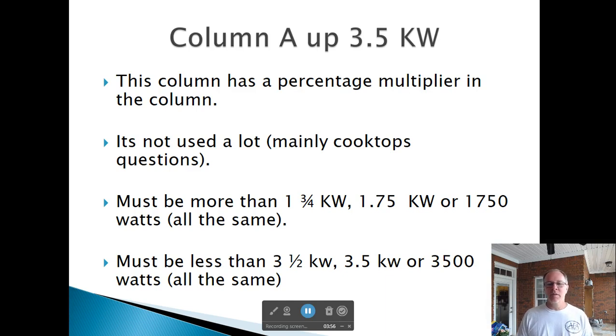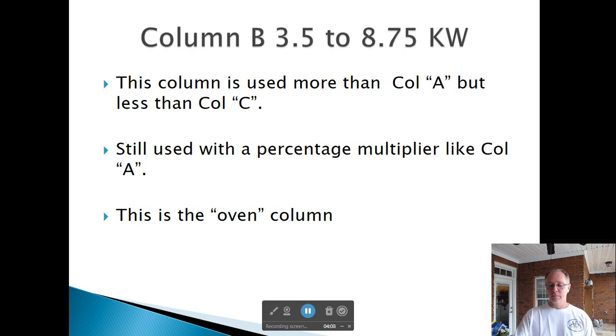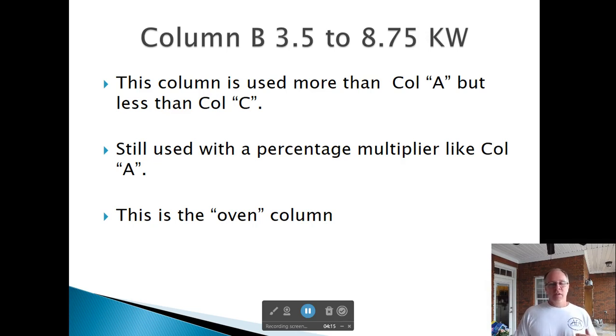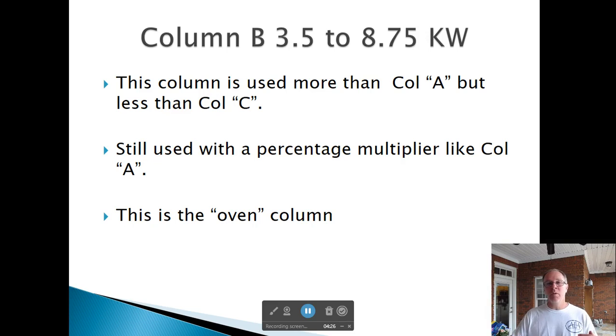Column A must be more than 1,750 and less than 3,500 watts. Column B is the oven part — a little bigger but still a percentage. You add all the kW up even if they're different types; one apartment may have a 5,000-watt oven and another has 3,500. They're unequal, but you add them up and apply the multiplier.